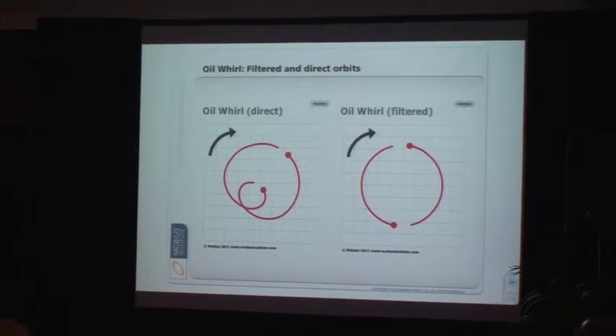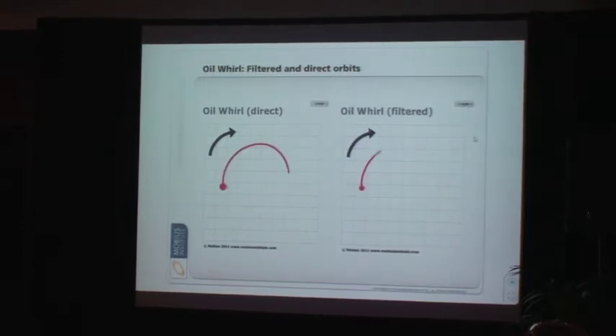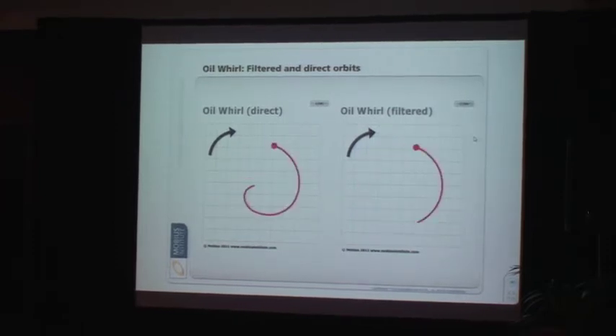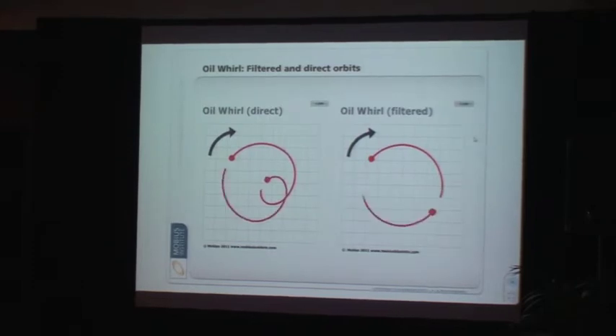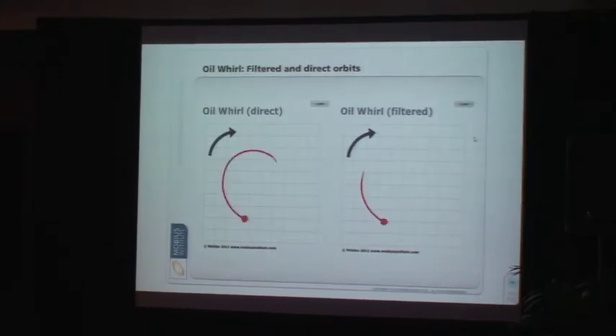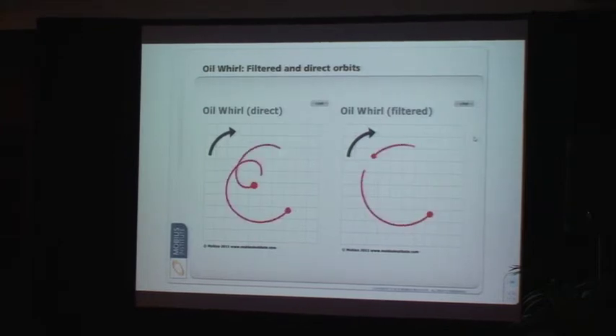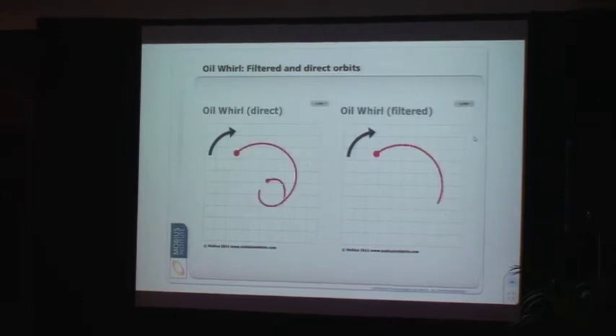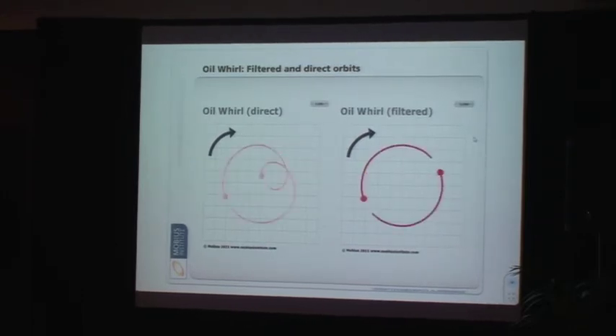If we look at the direct signal, we've got a combination of the motion and the submotion, because we're looking at all the vibration. But if we look at this in live mode instead, we'll see the orbits—not only do we see our 2 dots, which aren't completely opposite each other, we'd see the orbit rotate. If we know the direction of rotation, that's the big black arrow, and see which way the orbit itself is rotating, against that direction, we therefore know it's less than half the running speed.